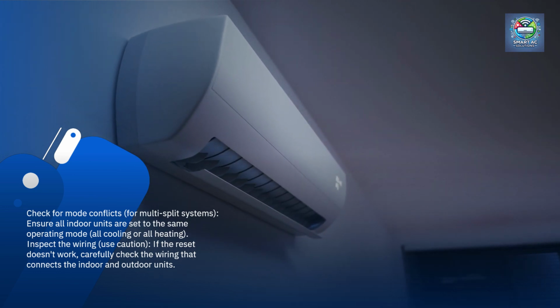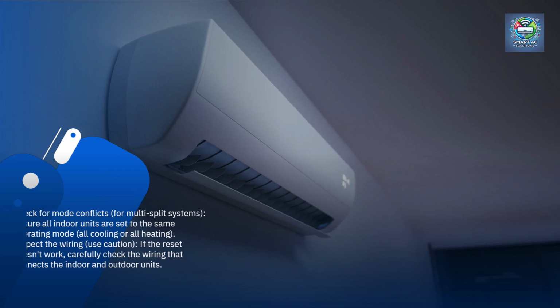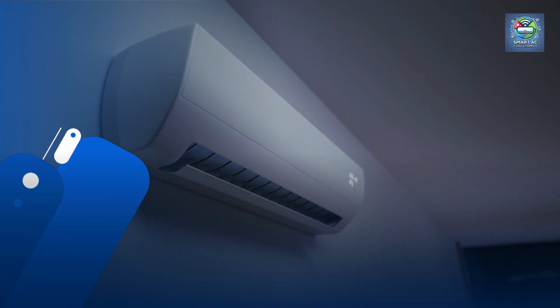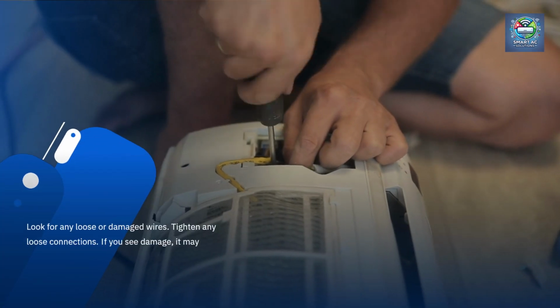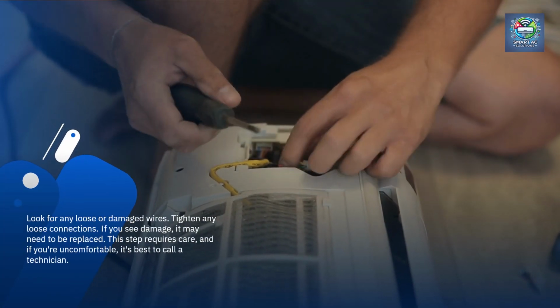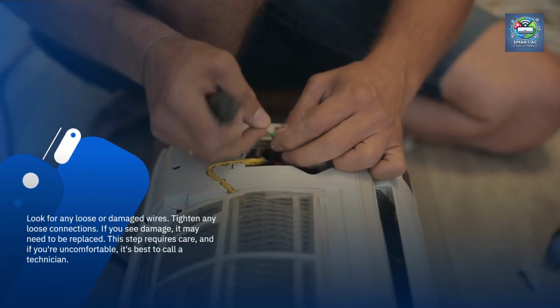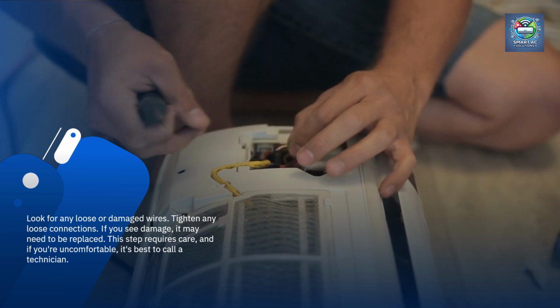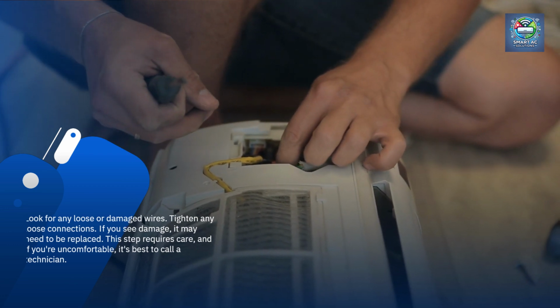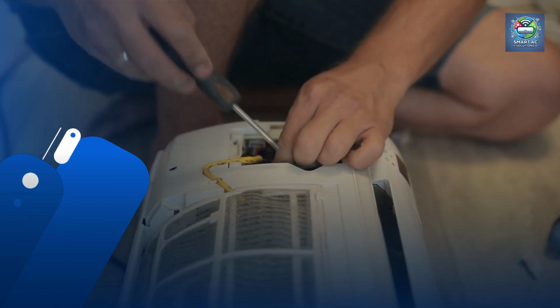Inspect the wiring. Use caution. If the reset doesn't work, carefully check the wiring that connects the indoor and outdoor units. Look for any loose or damaged wires. Tighten any loose connections. If you see damage, it may need to be replaced. This step requires care, and if you're uncomfortable, it's best to call a technician.